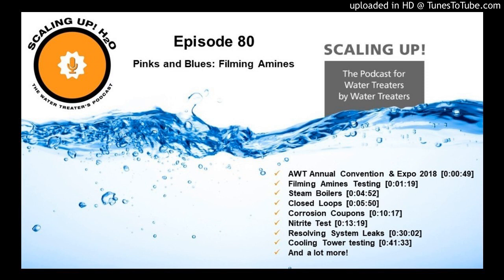Now, here's the thing. Filming amines are cleaners, so they are going to clean the surface. How quickly do you want those to clean? A lot of the manufacturers recommend that you calculate the ideal dose and then cut that in half. Well, folks, we here at Blackmore Enterprises actually cut that either to a third or a quarter because, as you all know, it is so much easier to add than it is to take away.